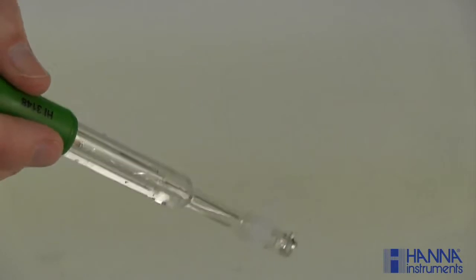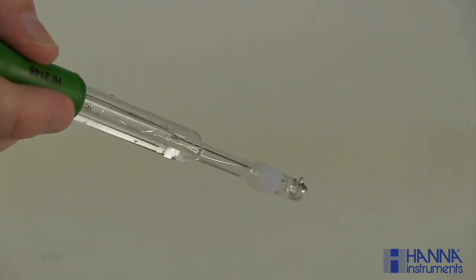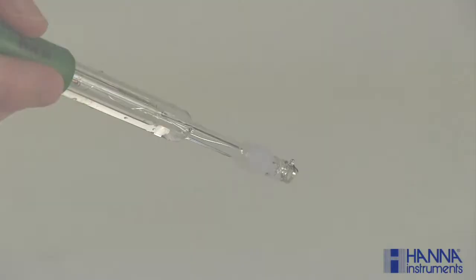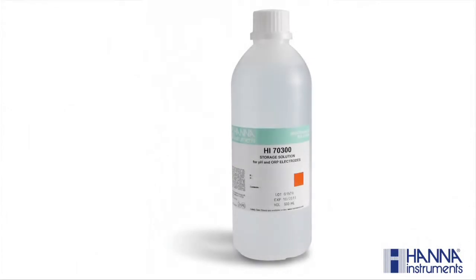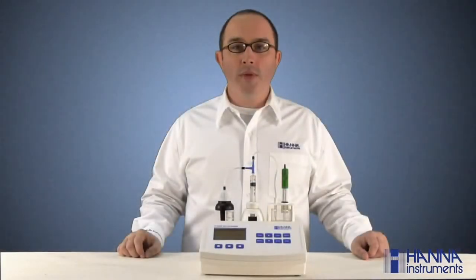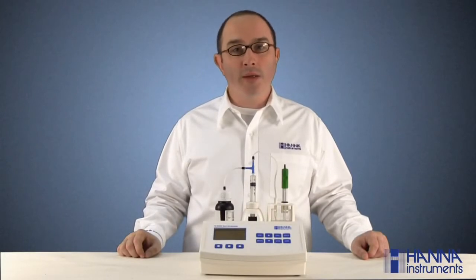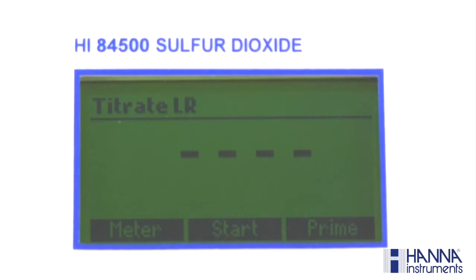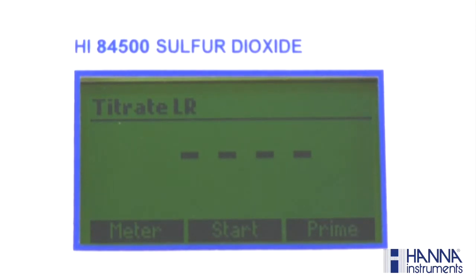To remove these bubbles, simply shake down the electrode as you would do with a glass thermometer. If the bulb is dry, soak the electrode in our HI-70300 storage solution for at least 1 hour, and then connect it to the titrator. And that's it. Now we're ready to install and calibrate our dosing pump. A pump calibration must be performed every time the syringe, pump tube, titrant bottle, or ORP electrode is changed. It is also recommended to perform a calibration once per day.